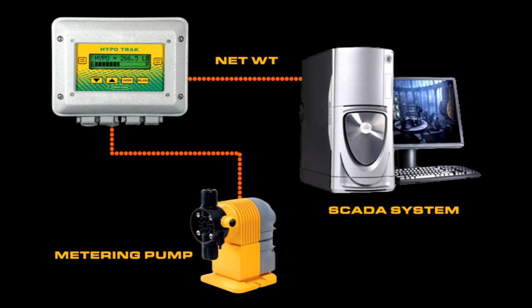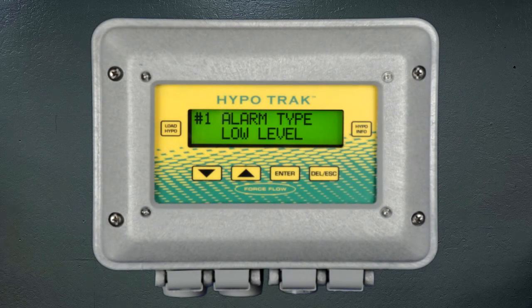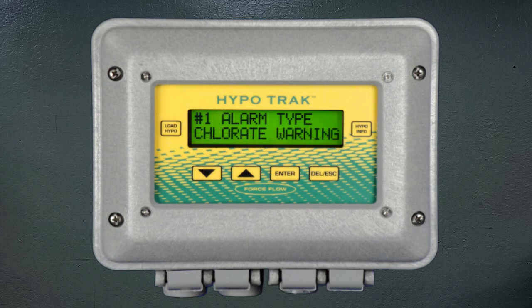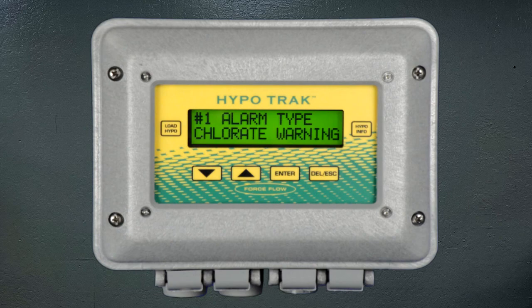This feature is ideal for systems that don't integrate residual analyzers or compound loop controls. The Hypo Trak also has four alarm contacts that will warn operators of the following conditions: low tank level, high tank level, pump vapor lock, and high chlorate warning. The pump vapor lock alarm detects a low feed rate condition via loss in weight and can be used to warn of a possible vapor lock metering pump. The chlorate warning alarm is a timer initiated when new Hypo is loaded, keeping track of how many days your Hypo has been on site. Chlorates are a byproduct of the Hypo degradation process and are beginning to be regulated because they are known to impair thyroid function.